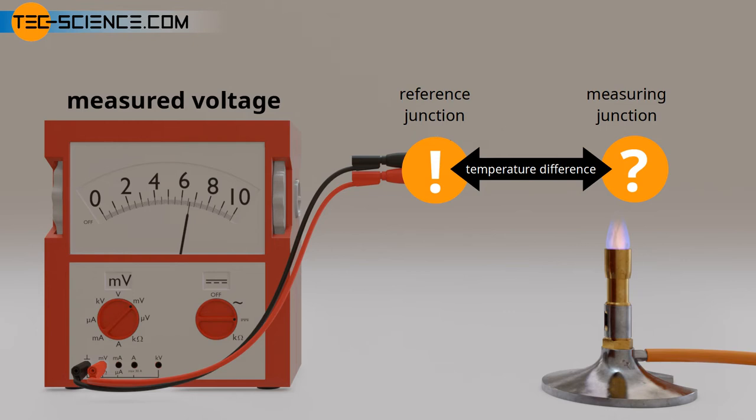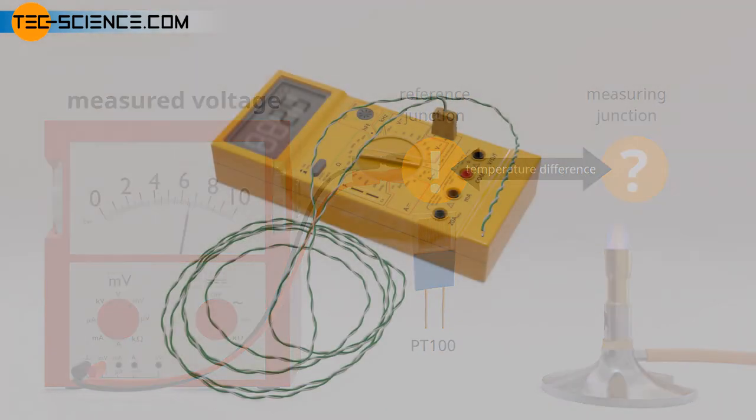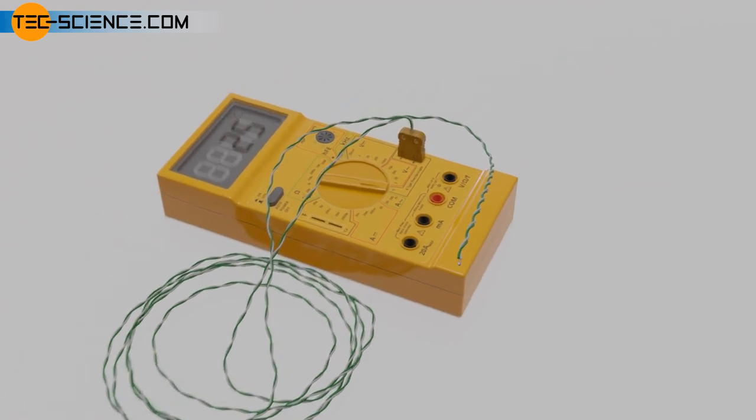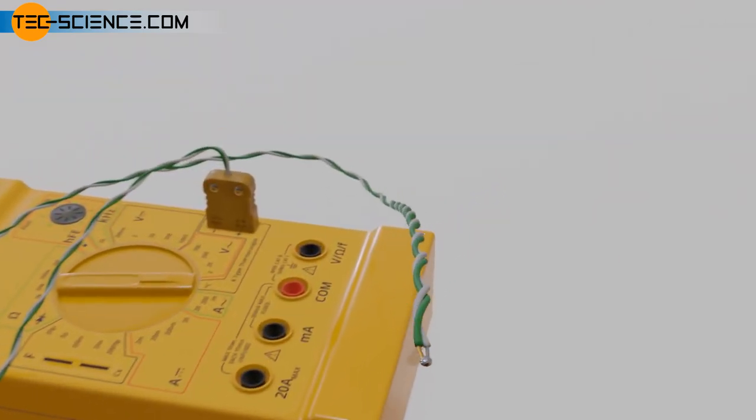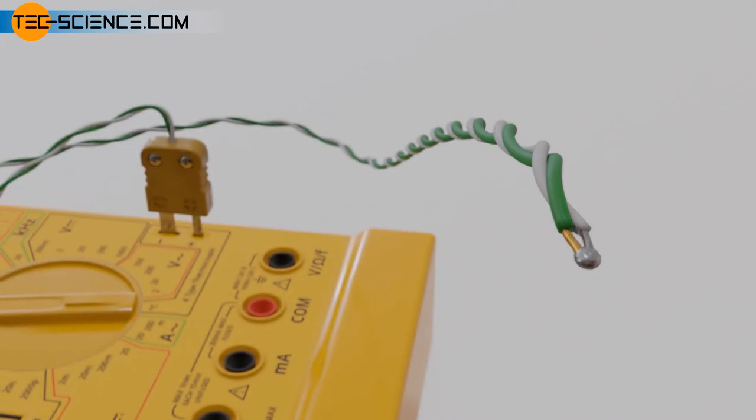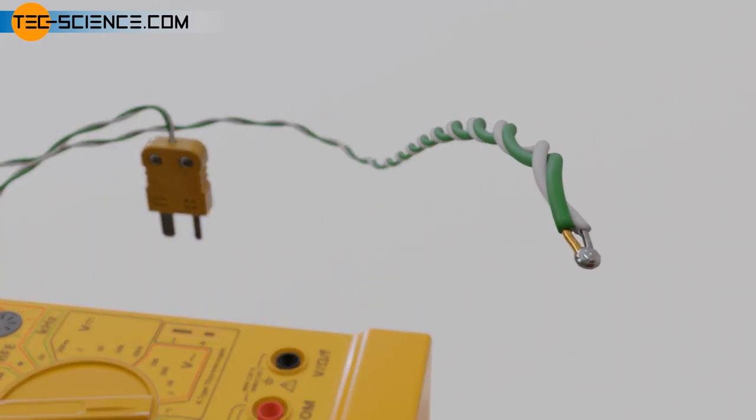The cold junction temperature can, for example, be determined with a PT100, whose electrical signal can then be processed directly with the thermoelectric voltage in order to output the temperature at the measuring point. The cold junction temperature sensor is usually located inside the housing of the measuring instrument. The actual thermocouple is then connected to the measuring device via a plug-in connection.